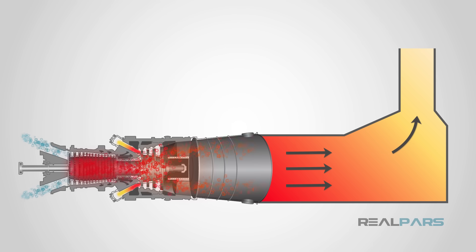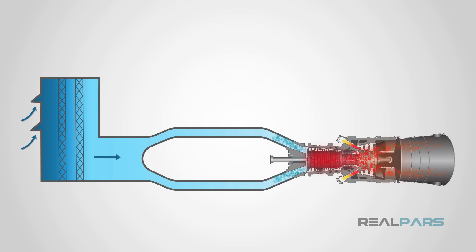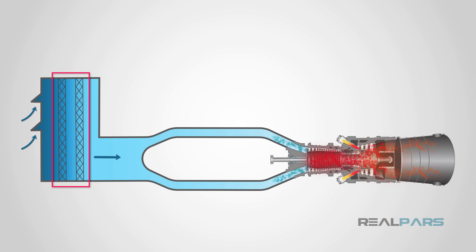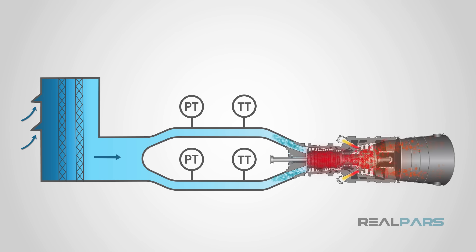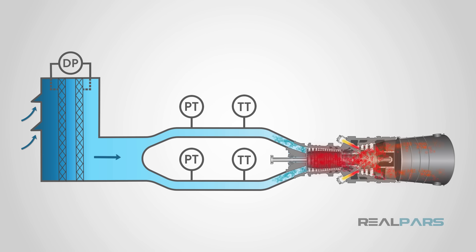As mentioned earlier, air is let into the gas turbine through an air intake. The air is prone to contamination or having unwanted particles which can harm the system and degrade overall performance. Screening and filtration are basic requirements for incoming air. Proper instrumentation is mounted on the air duct to monitor draft pressure and temperature. In harsh environments, the air might need to be preheated or conditioned, and differential pressure monitoring of air filters will warn the turbine operator of filter clogging.